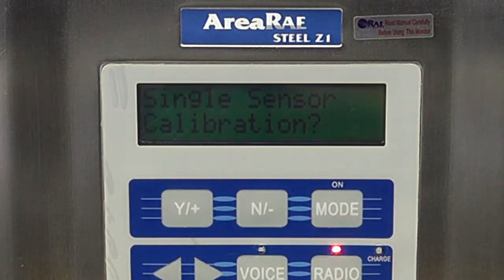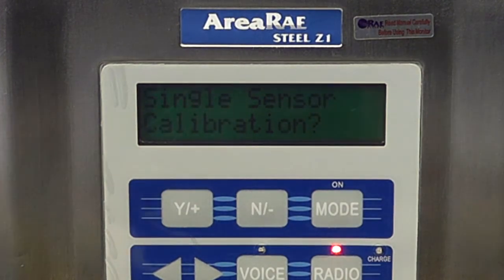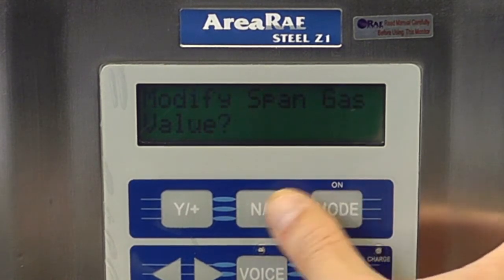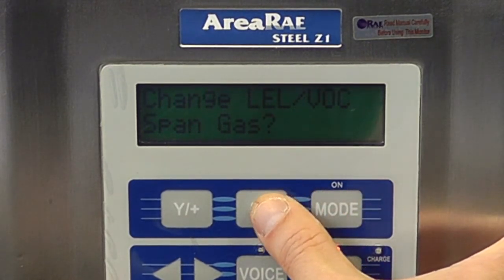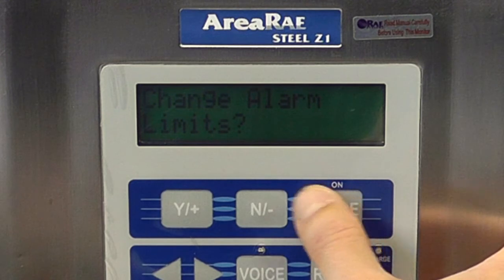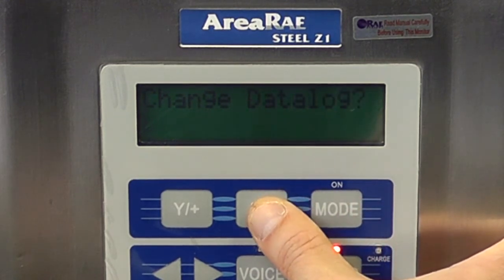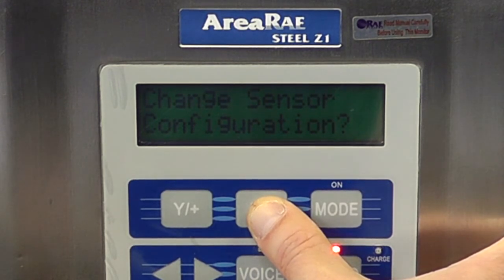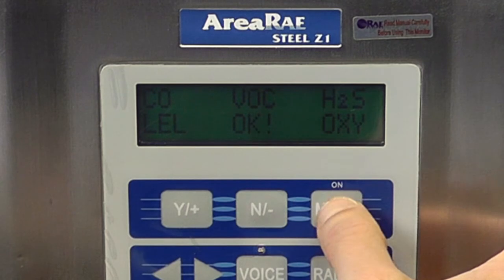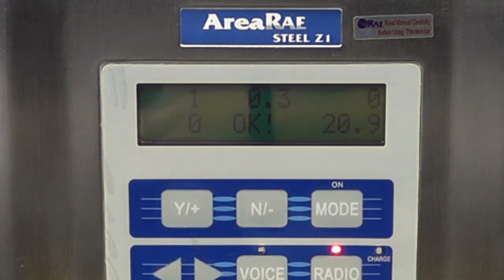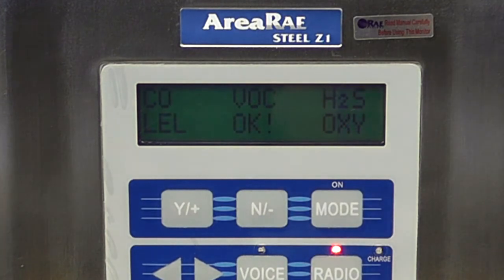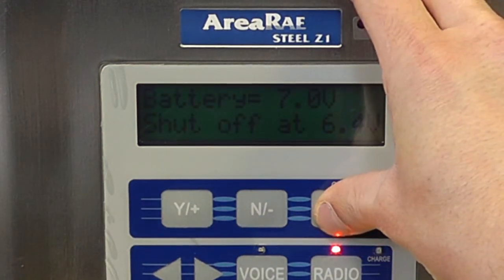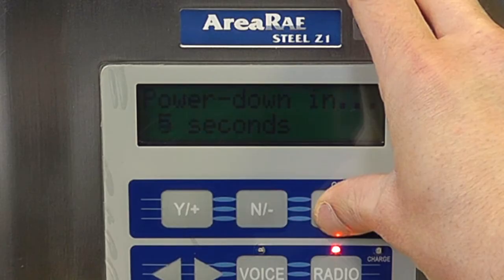So that completes the calibration of the instrument. If we want to change any of the span values, this can also be done from this menu. We can change any of the alarm limits, change the data log settings or the general monitor setup, change the sensor configuration, including adding or removing any sensors we don't want to monitor, and then to return to normal operation, just press the mode button, single click. And we can see the instrument is functioning exactly as expected. So to switch the instrument off, press and hold the mode button.